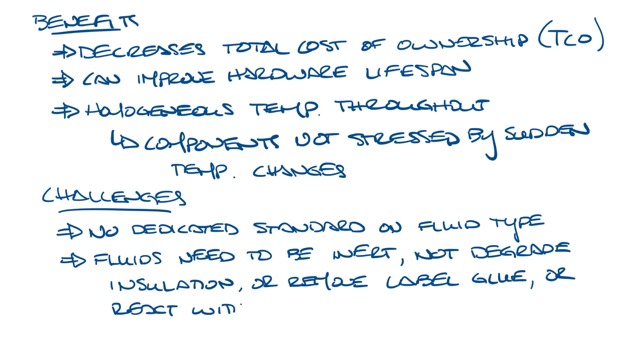But there are some challenges to immersion cooling. There isn't a dedicated standard on what type of fluid to use. The fluids used in immersion cooling need to be inert, not degrade the insulation, or remove the glue holding the labels on the equipment and the cables, and it can't react with inks on the motherboard, chips, or other components. Fluid management is another consideration. What if the fluid leaks, and how do you dispose of it?